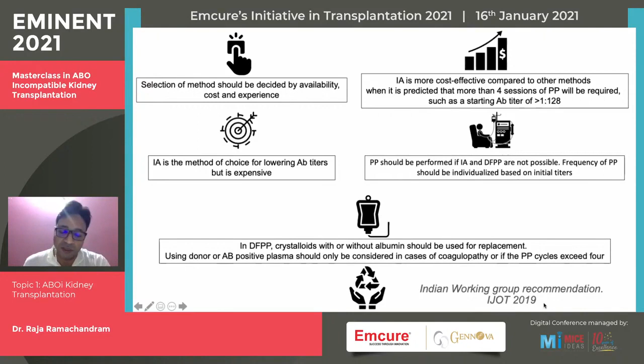Plasmapheresis may be performed if immunoadsorption and double filtration plasma exchanges are not possible. The frequency of plasmapheresis should be individualized based on titers. In double filtration plasmapheresis, crystalloids with or without albumin should be used as replacement. AB positive plasma followed by donor plasma should be considered in case of coagulopathy or if the plasmapheresis session is more than 4. And immunoadsorption columns may be reused, and saline washes followed by ETO sterilization and storing in dark is recommended by the Indian Working Group recommendation.